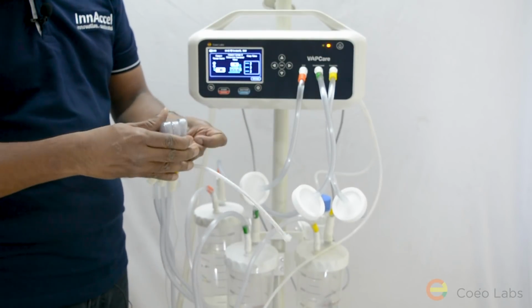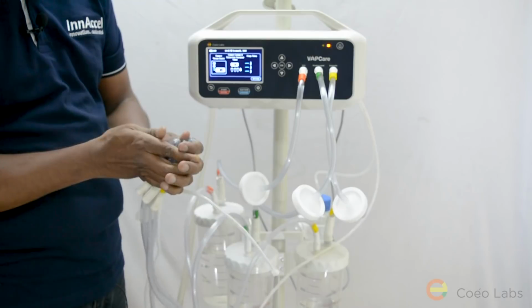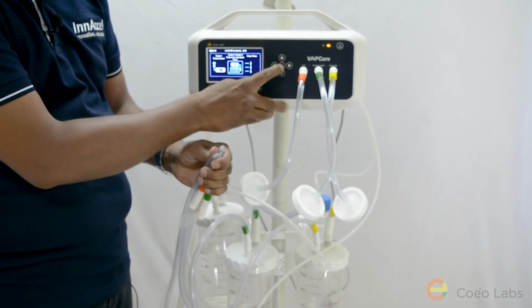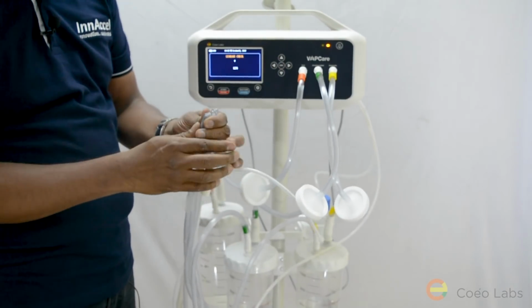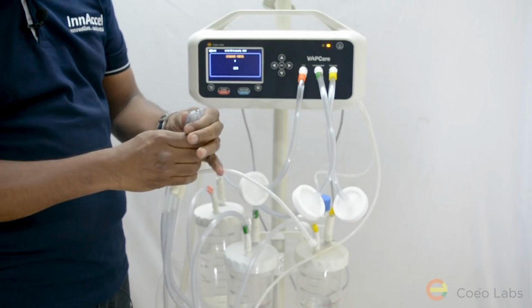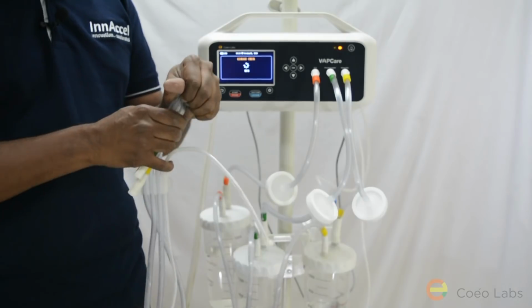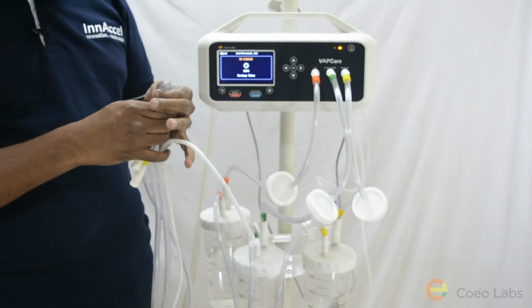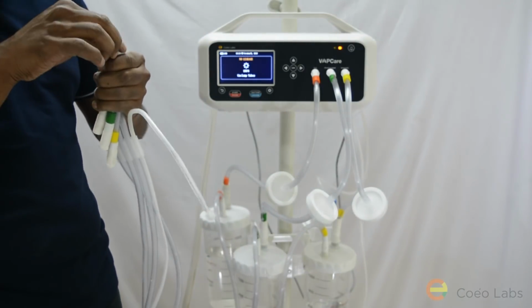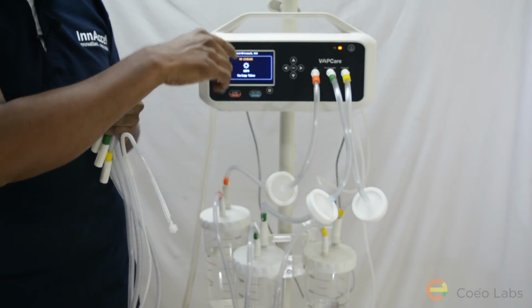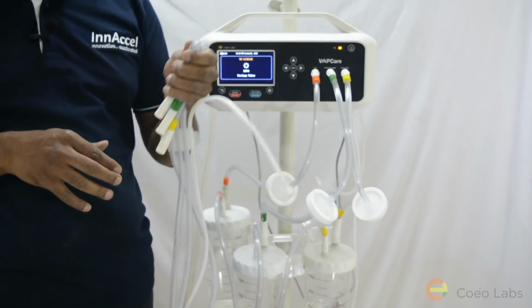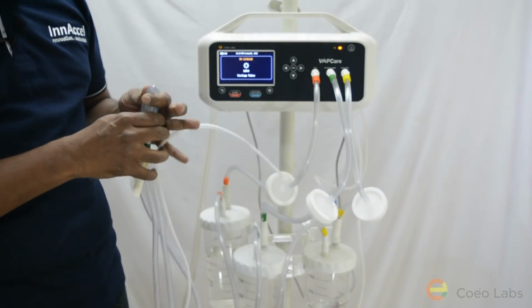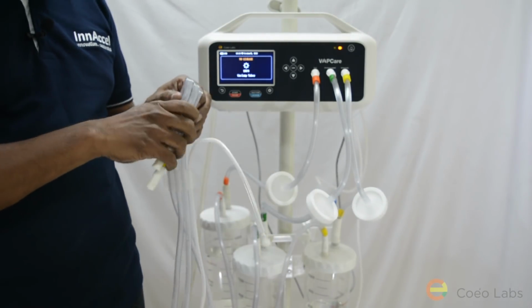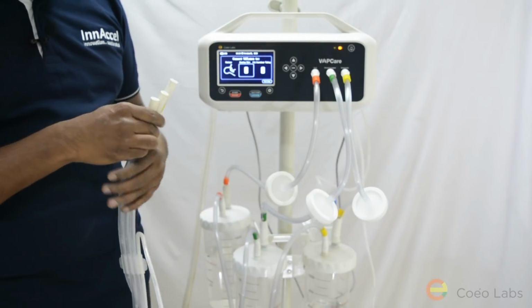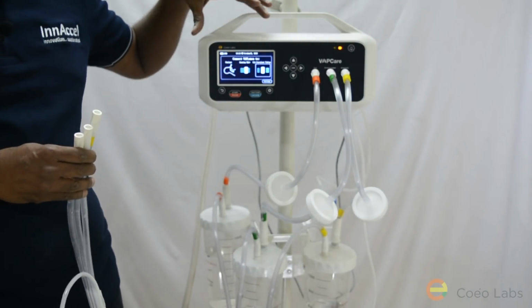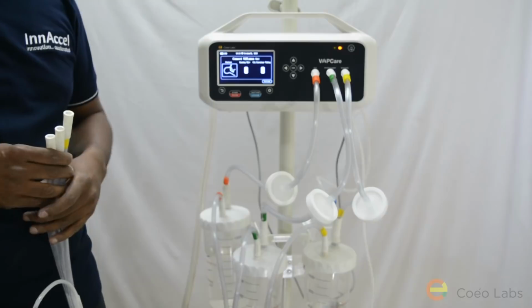Then we clamp the tubes and press OK. The device starts the leakage check. This leakage test checks the integrity of the entire system, from the tubings to the device, for any leakage in the connections. Once the system displays unclamp the tube, we unclamp the tubes, and the system shows the next steps for the patient connections.